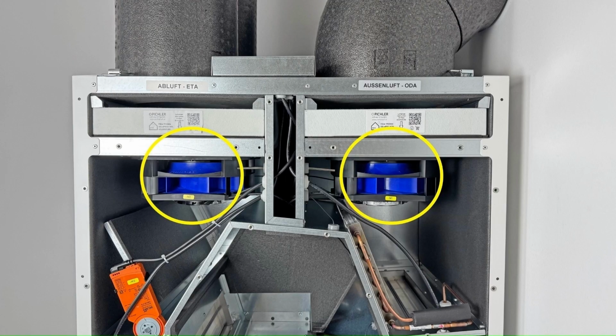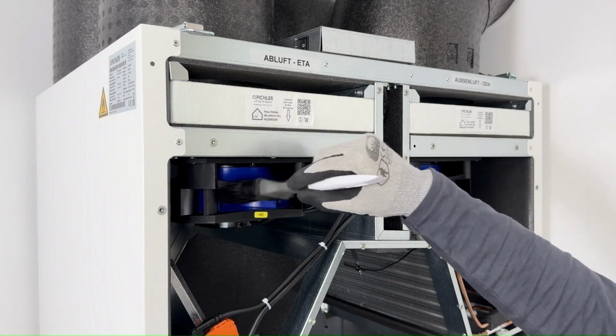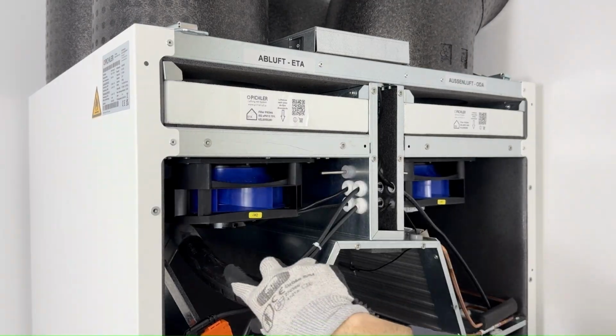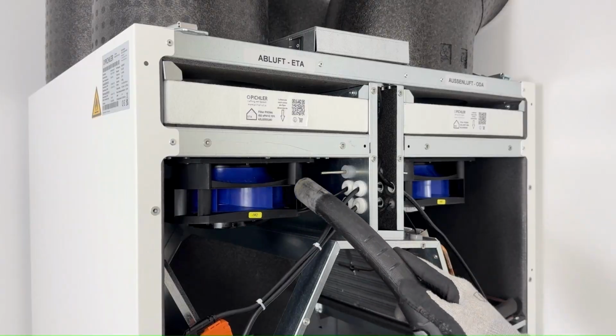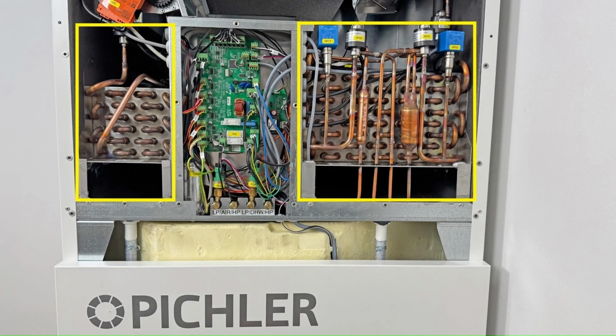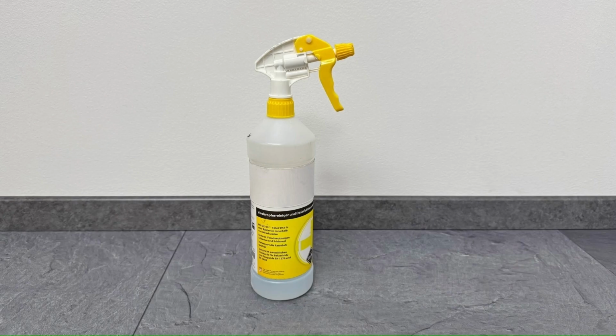Cleaning of fans. Maintenance and cleaning work on the fans is limited to the housing and the rotor. Please use a soft brush to clean the rotor. The fan housing can also be cleaned with a vacuum cleaner. Cleaning of heat exchangers and condensate trays. Only approved cleaning agents and disinfectants from specialist retailers may be used to clean the heat exchangers.